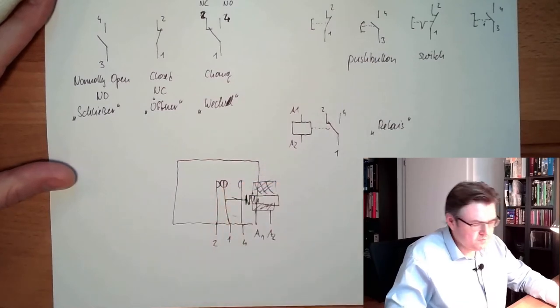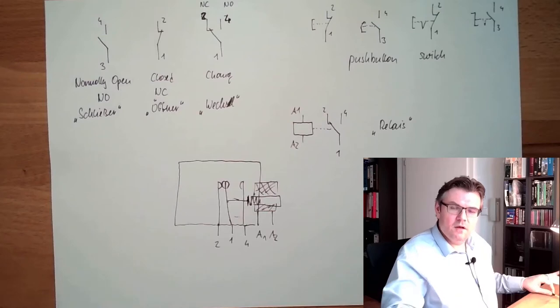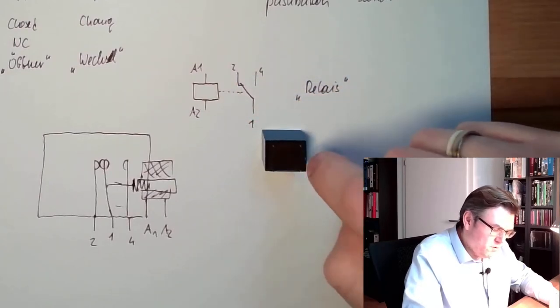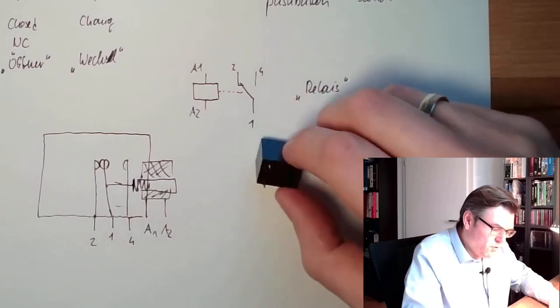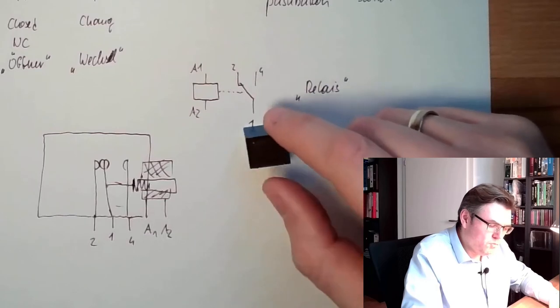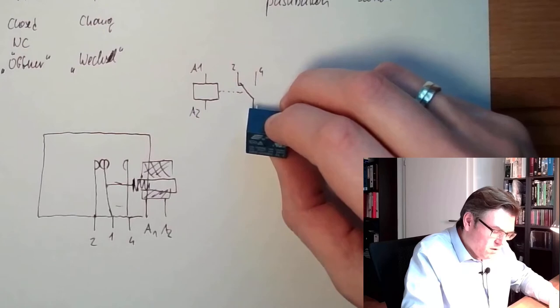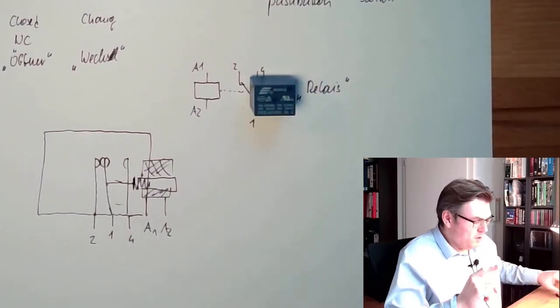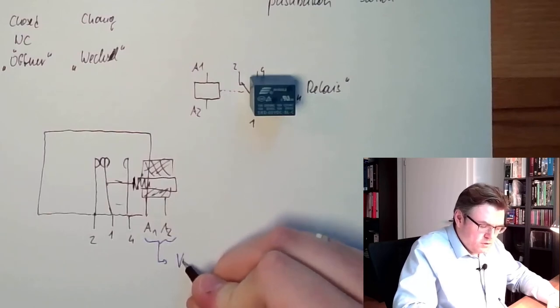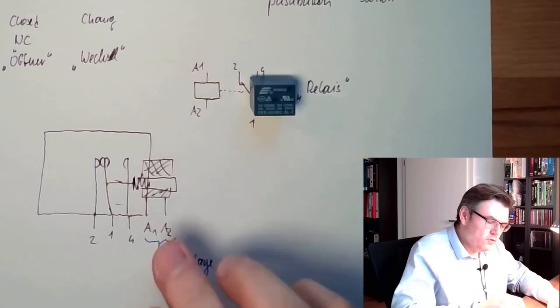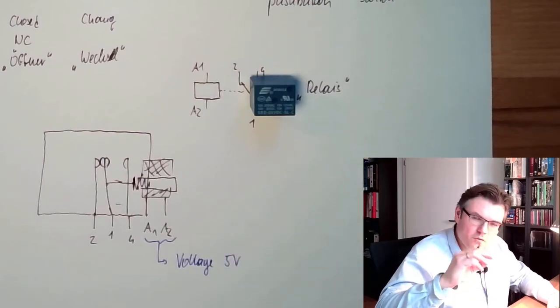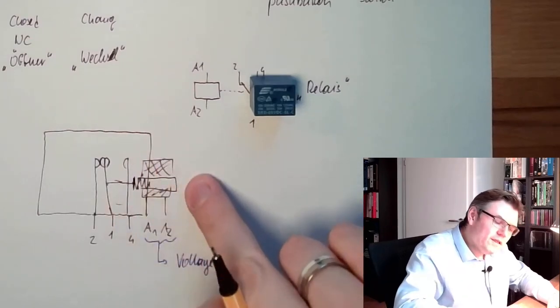These contacts inside can switch within the circuit. A relay looking like this is one possible relay. You see there's somewhere a coil and connections one, two, and four — so A1 and A2, one, two, four. One of these is normally closed, one is normally open. This is a very small relay. We have to distinguish between two things: the electrical properties of the coil — what voltage is needed to turn it on and off — for instance, this one here is a 5 volt relay, but the usual ones are 24V DC or 24V AC.